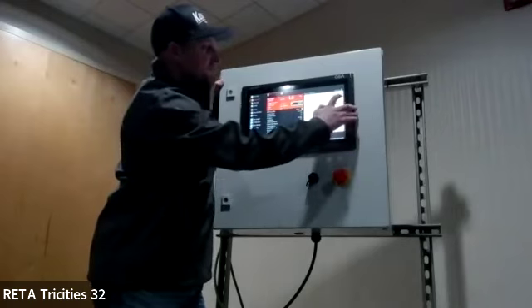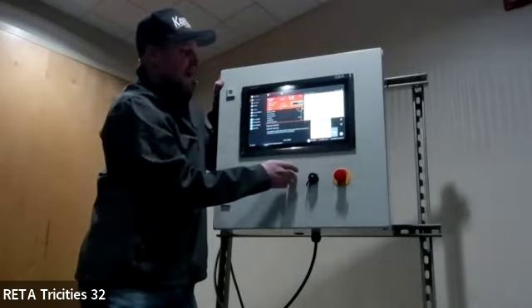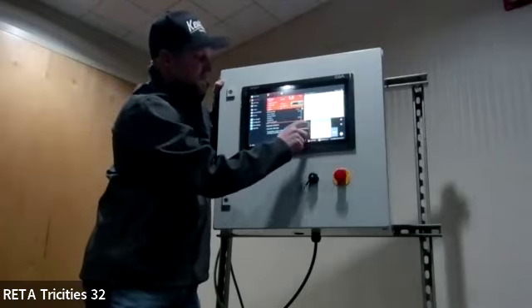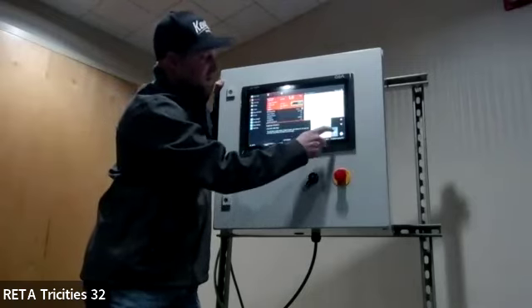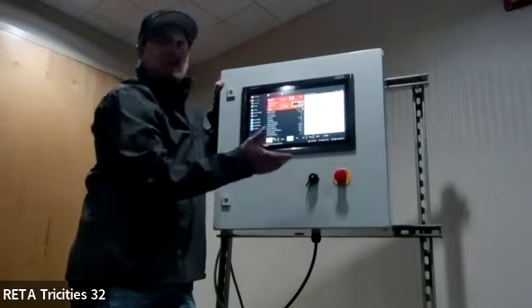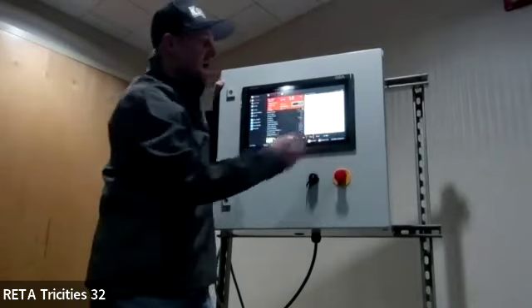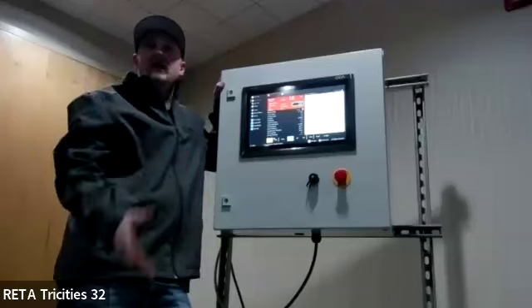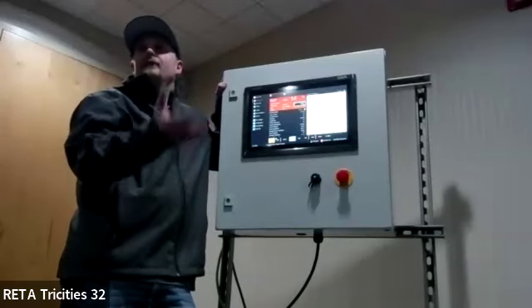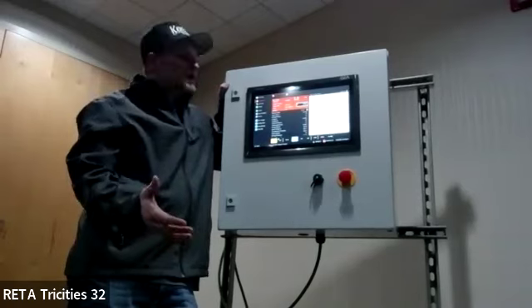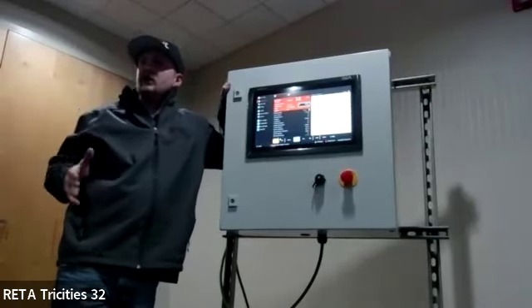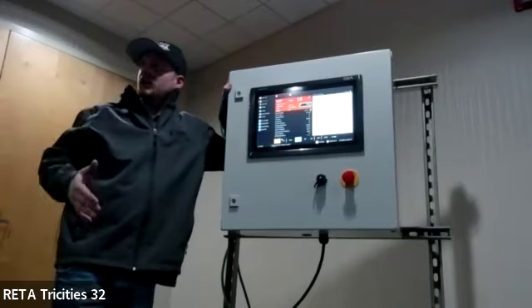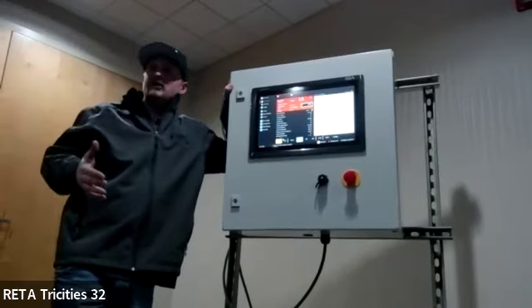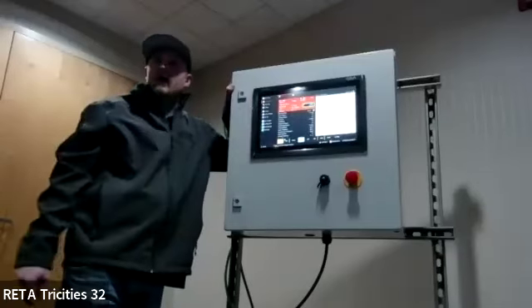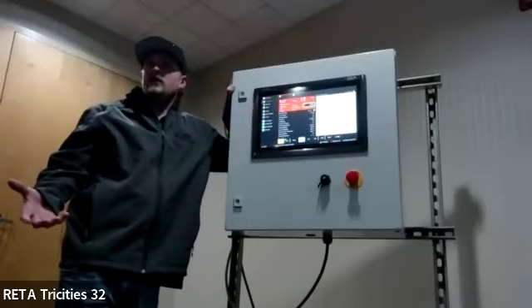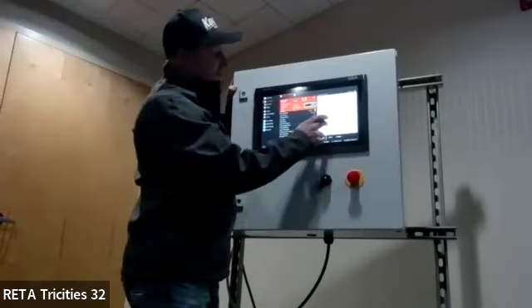The automatic start stop. So if you come over here and enable that, you can do it off of set points or offsets. Majority of the time, it's always going to be off of set points, right? So you want to automatic start at 30 pounds, and you want to automatic stop at 5 pounds. The critical thing about that is to make sure your suction shutdown is below the automatic stop, because if it hits the suction shutdown, it's going to shut down, turn it red, and it will not auto stop. It will not auto cycle back on.